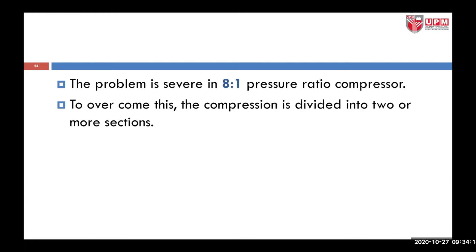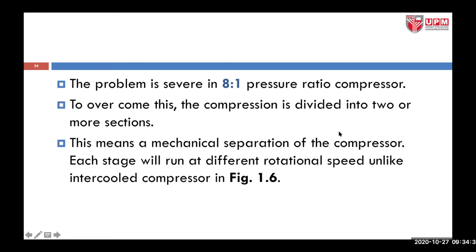To overcome this, whenever you decide to still use an axial type compressor, the compression is divided into two or more sections. This means a mechanical separation of the compressor, so each stage will run at a different rotational speed, unlike the intercooled compressor in Figure 1.6 that we looked at before.